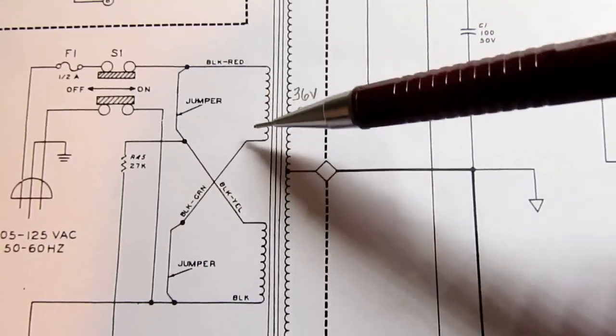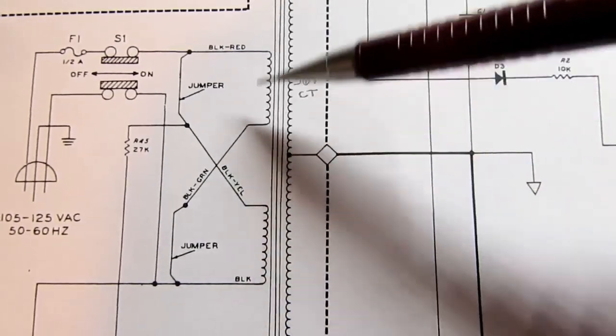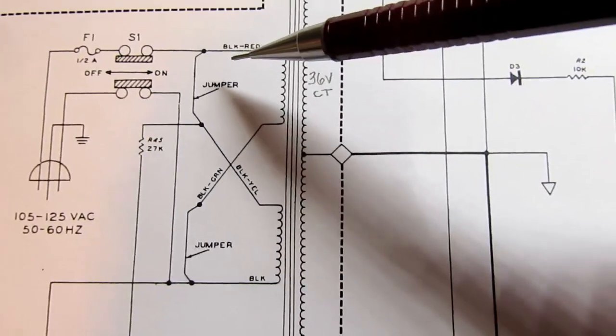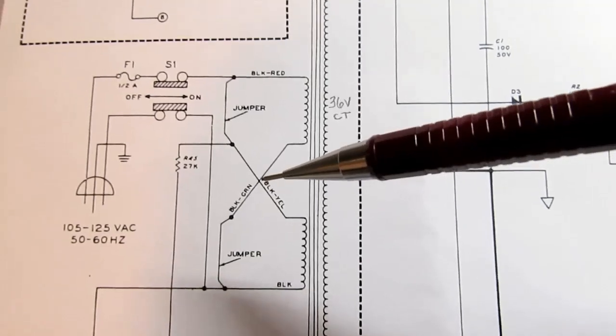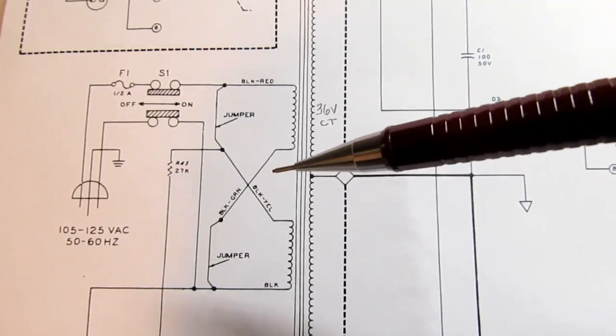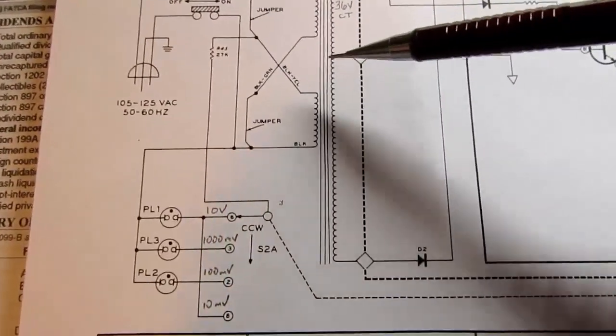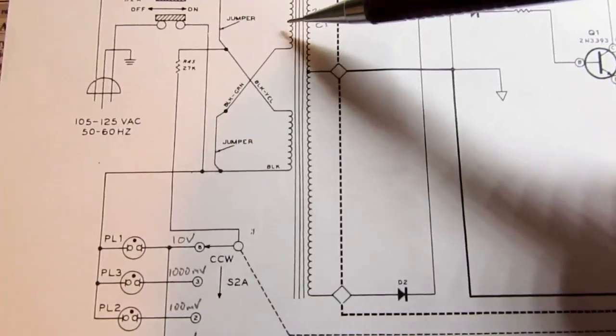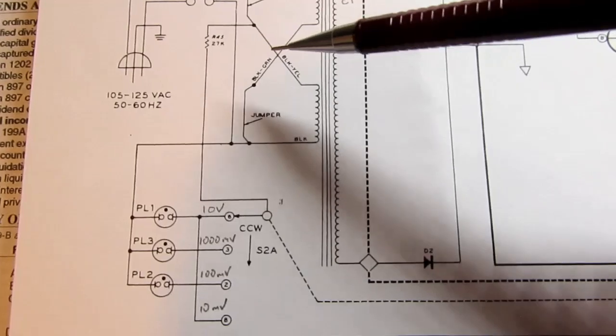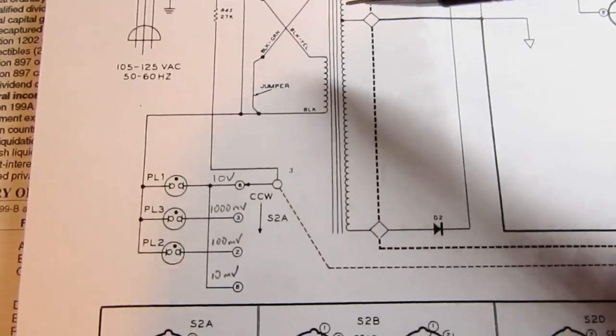And then you have your 2-winding primary winding, which can be wired in series or parallel. It would be wired in series if you're using the higher voltage option, but you have the 2 coils wired in parallel if you're running it at 120-ish volts.